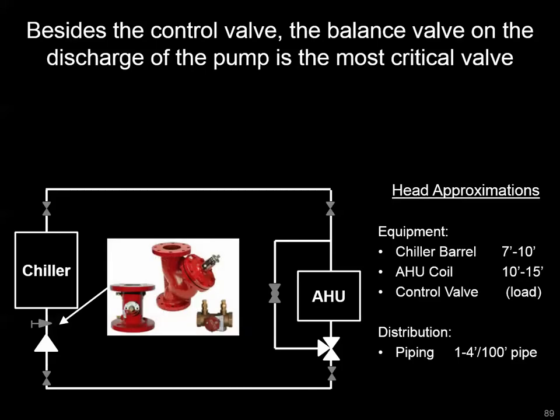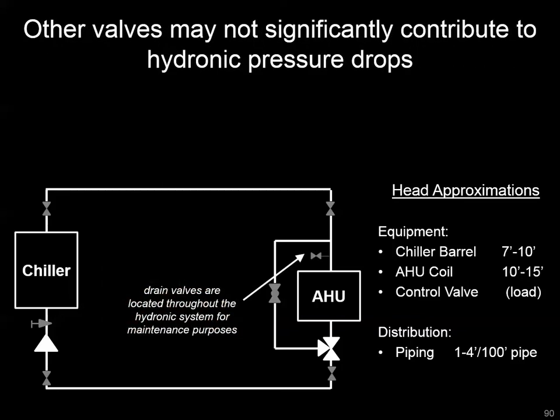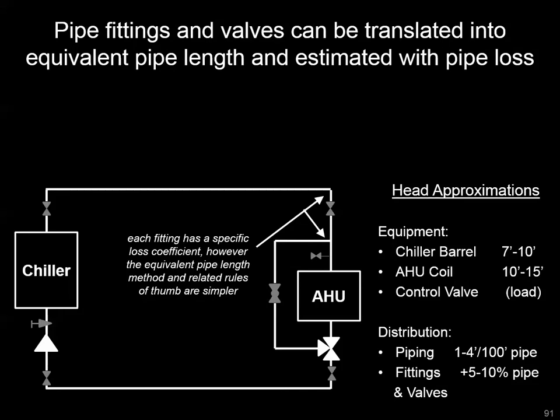Here's what some of those balancing devices might look like — triple duty valves, circuit setters. You'll also have drain valves located throughout the system used for maintenance purposes; they might be a source of leaks, so pay attention to those. There'll also be a number of tees and elbows running through the system. Instead of counting the pressure drop across each one, there's a rule of thumb that says somewhere between 5 and 10 percent of your pipe length should be added to your distribution calculation to account for that pressure drop.